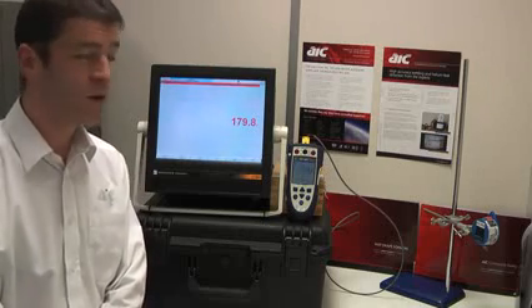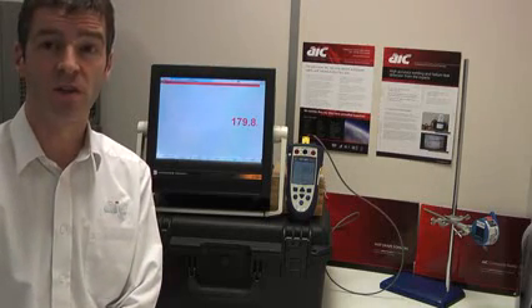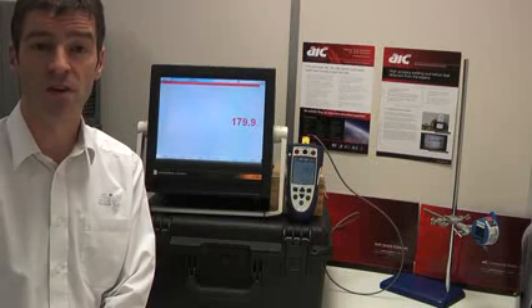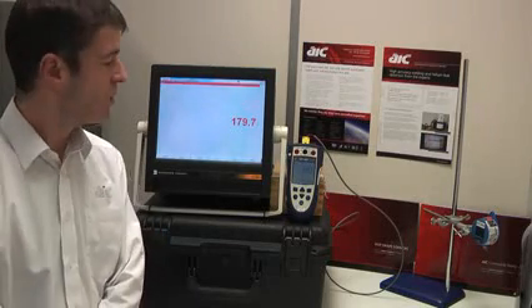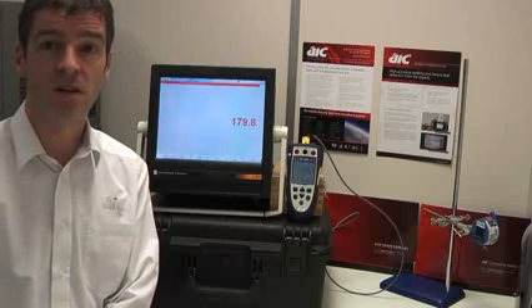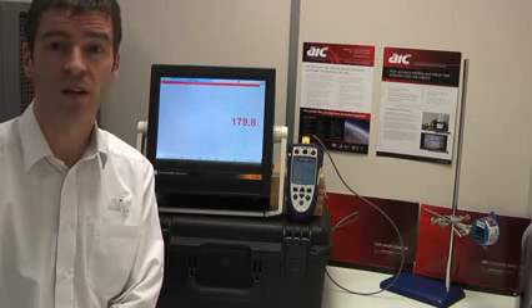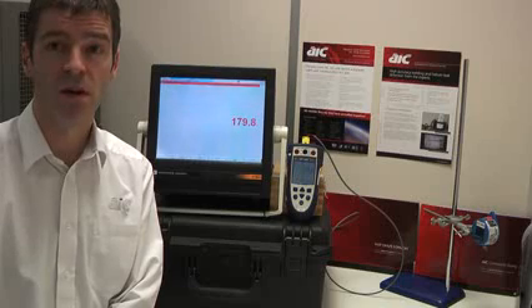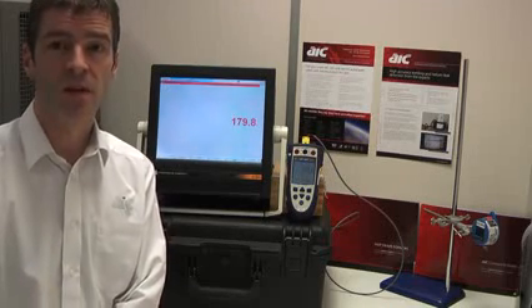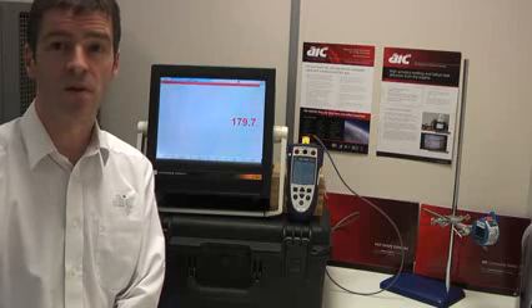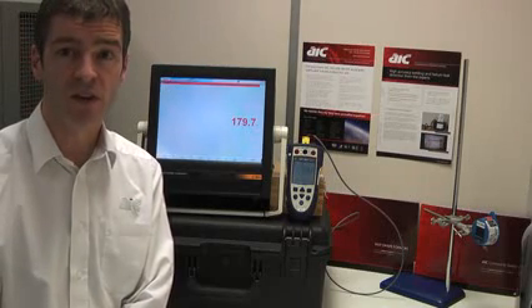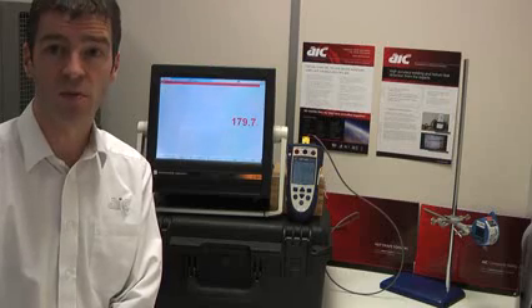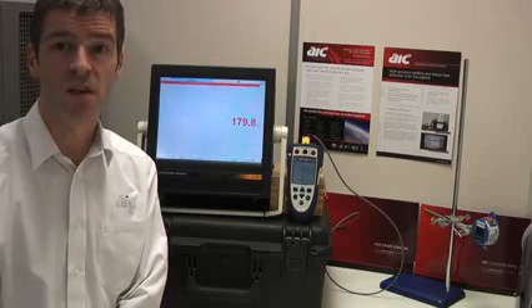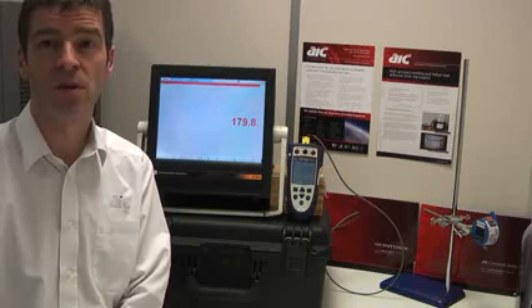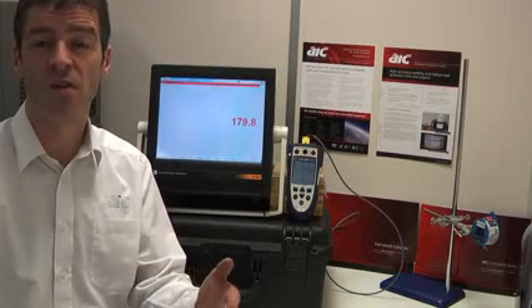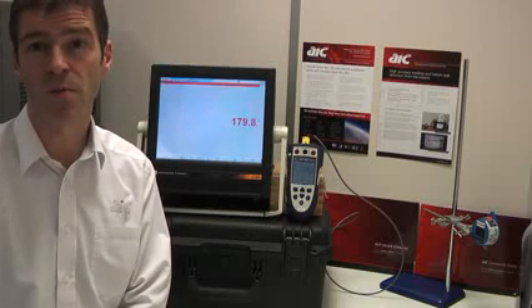So, how can we calibrate this thermocouple cable and assure ourselves that it's not introducing sources of error in our measurement and control? Well, ASTM, British and other thermocouple standards all state that standard techniques for calibrating thermocouple cable are only applicable when the cable is new. If you want to remove the cable to calibrate it, you have to be very confident that you can exactly recreate the temperature gradients that the cable will experience in practice. Otherwise, the inhomogeneity in one part of the cable that would introduce an error in practice may not introduce an error during your calibration.